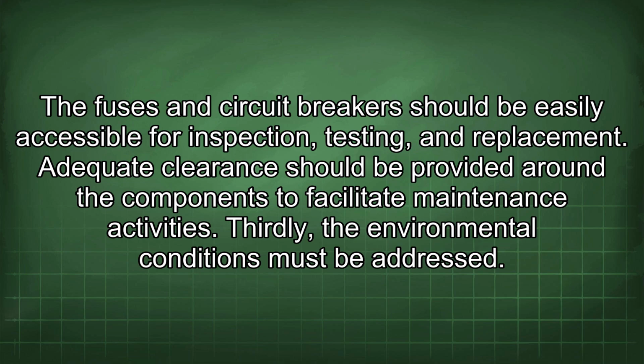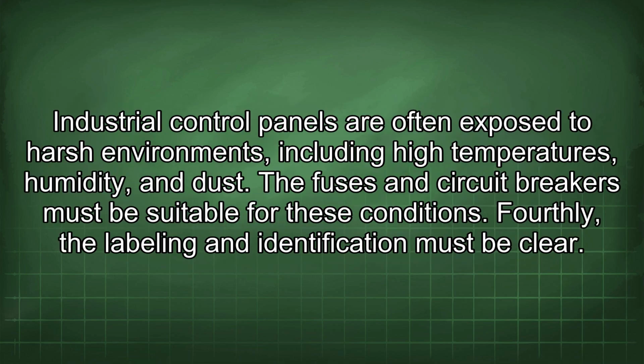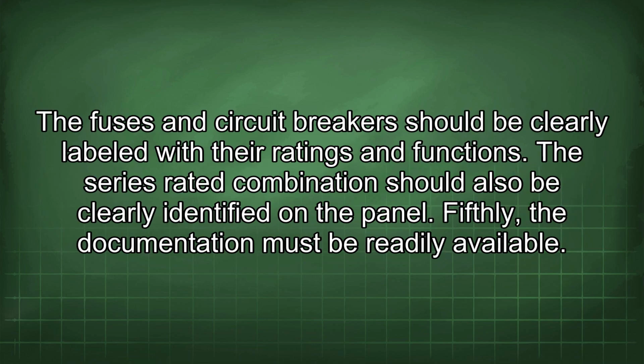Thirdly, the environmental conditions must be addressed. Industrial control panels are often exposed to harsh environments, including high temperatures, humidity, and dust. The fuses and circuit breakers must be suitable for these conditions. Fourthly, the labeling and identification must be clear. The fuses and circuit breakers should be clearly labeled with their ratings and functions. The series-rated combination should also be clearly identified in the panel.